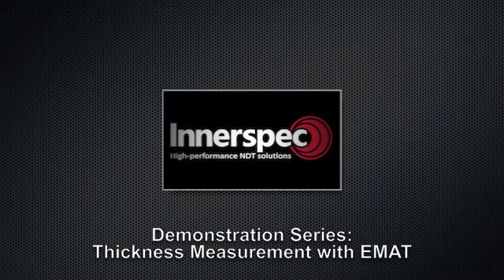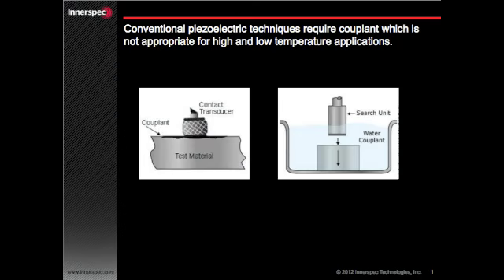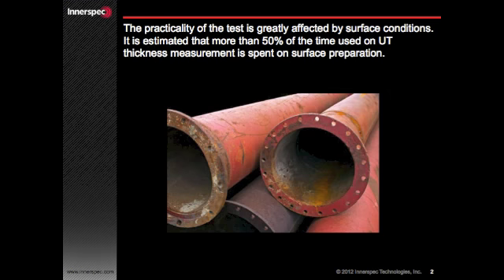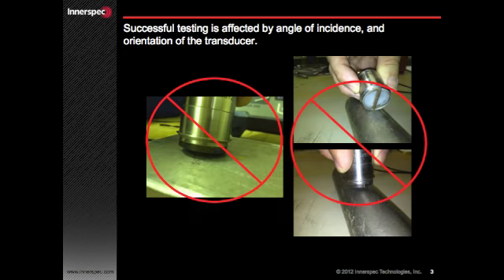Ultrasonic testing is the technique of choice to measure thickness when there's only access to one side. However, conventional piezoelectric systems generate the sound in the transducer, which has important drawbacks. Conventional UT techniques require couplant and are not appropriate for hot or very cold applications. The practicality of the test is greatly affected by surface conditions. It is estimated that more than 50% of the time used on UT thickness measurement is spent on surface preparation. And successful testing is affected by the angle of incidence and the orientation of the transducer.